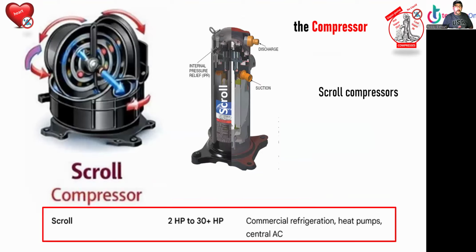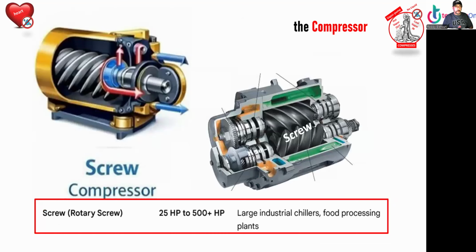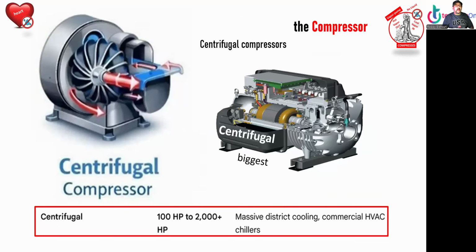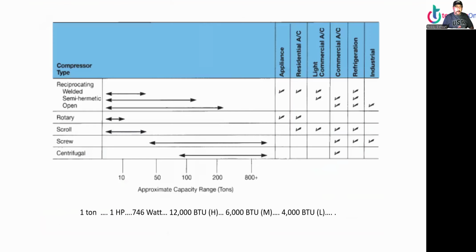Now we have the scroll. And it goes from 2 horsepower to 30 horse. The screw compressor, I'm not going to cover much, 25 to 100, but I do have a story about the screw and pictures. And the centrifugal is for major stuff. I'm not going to cover much. Alrighty, so this is showing you the sizes. The reciprocating from the chart. I'm not going to go through it. Different applications for different compressors, for different sizes, different usage. But what's important, at the bottom I wrote down: 1 ton equals 1 horsepower, same as 746 watts, 12,000 BTU for high temp, 6,000 BTU for medium temp, and 4,000 BTU for low temp. All right, let's move on now.